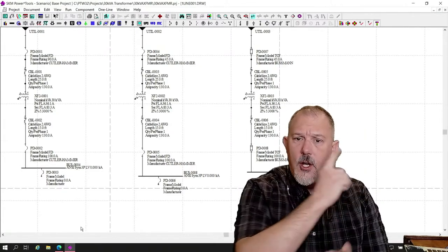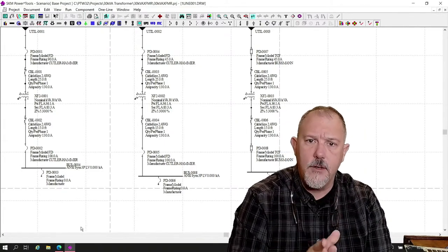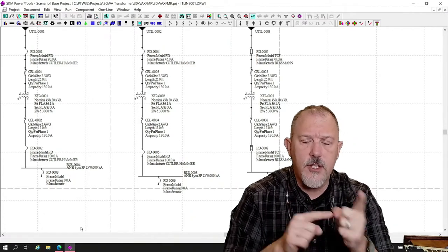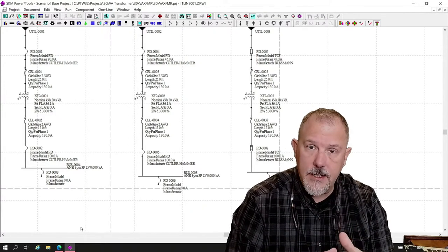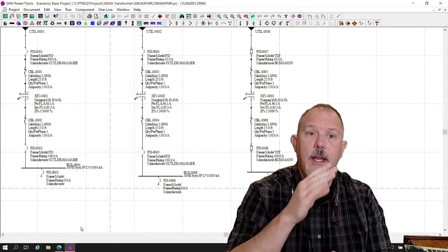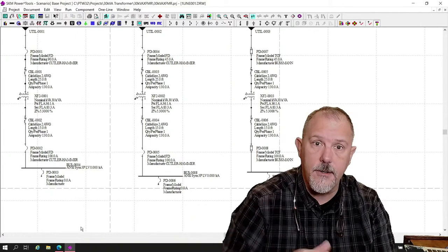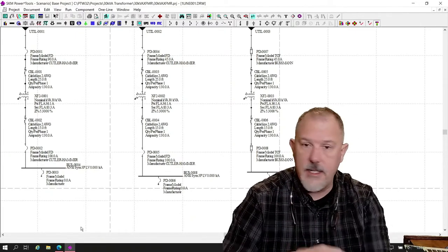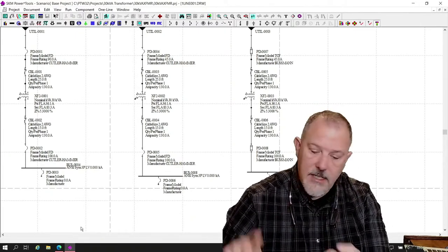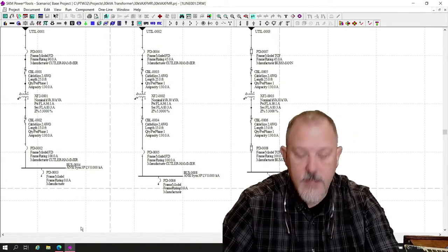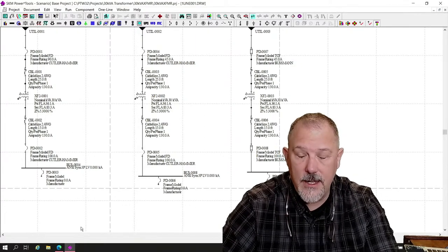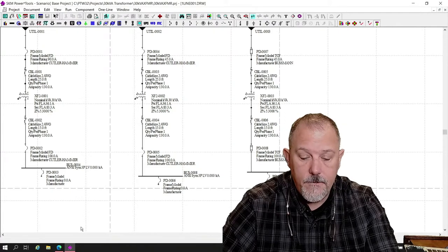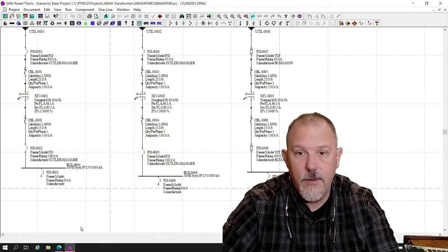We're going to plot some curves and help you understand circuit breakers and fuses, the time current characteristic curve, how to read a TCC curve, and how the curves relate to each other. I use SKM, but there's also Easy Power, EDSA, and a few others. These softwares are like Windows and Apple — if you learned on Windows, you tend to stick with Windows, and vice versa. I only have SKM because we pay for that, and I'm not buying more than one when it does the job.